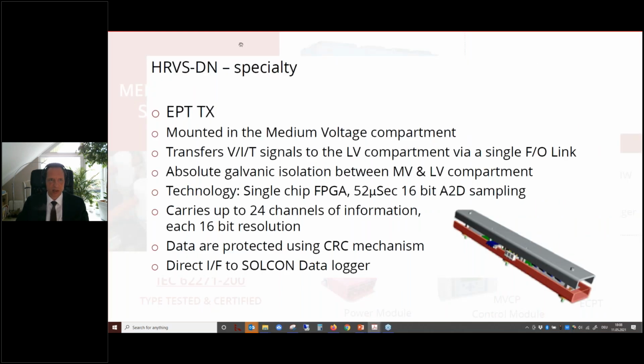One word on the EPT TX, what you see here in the picture. It's a specialty. This is a measuring device which is mounted in the medium voltage compartment. And the three green devices here are mounted on the medium voltage bus bars. From there, you detect the voltage and you give the information about voltage, current and temperature via fiber optics to the low voltage compartment. The nice thing about this is that there is absolute galvanic isolation between the medium voltage and low voltage compartment. There is no connection in between, which gives you additional safety.